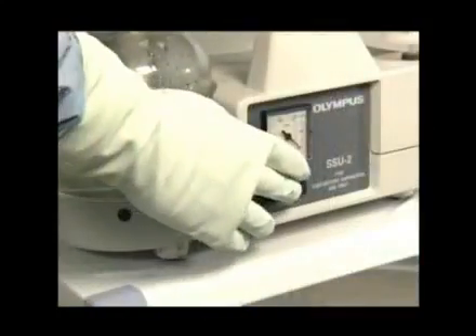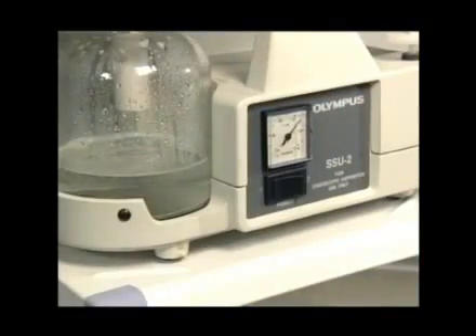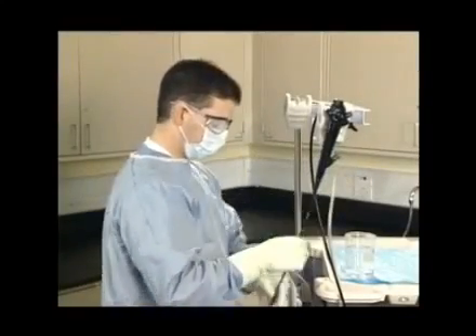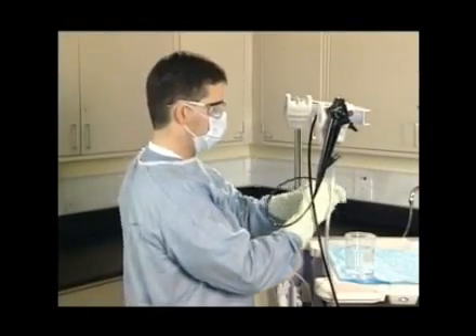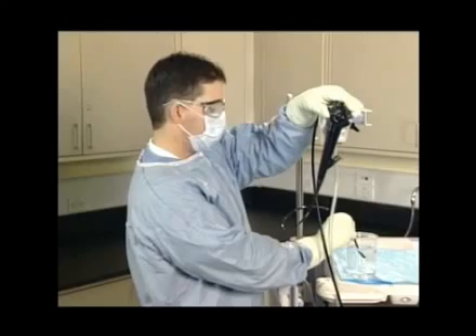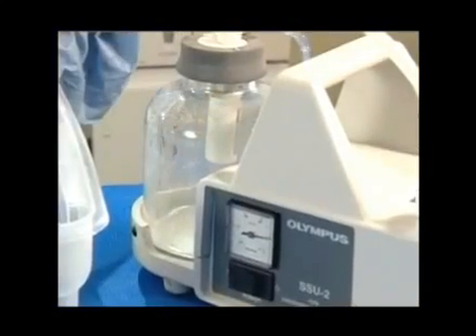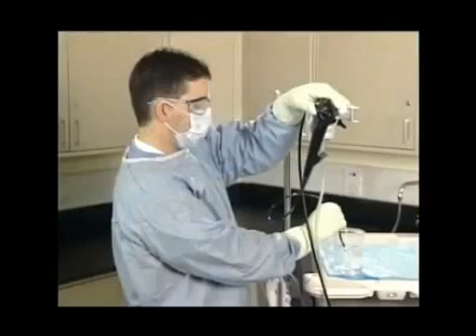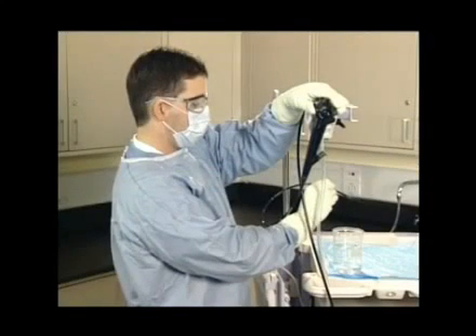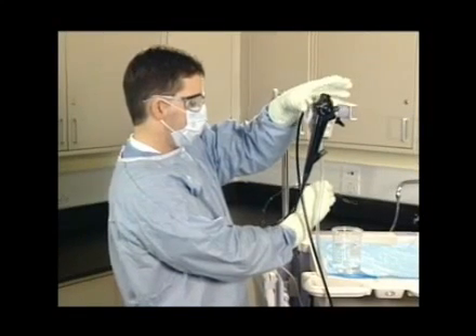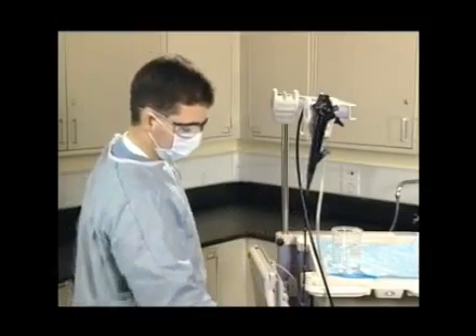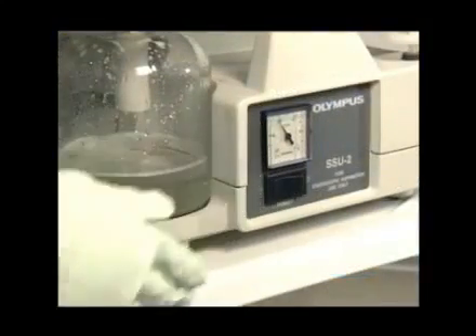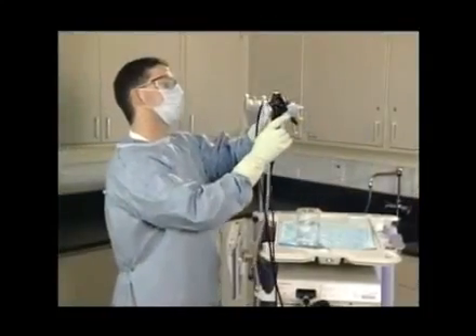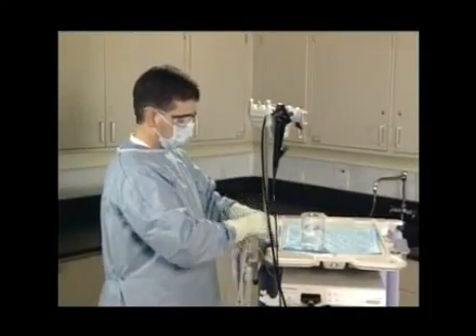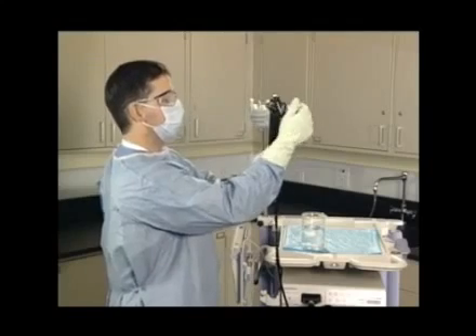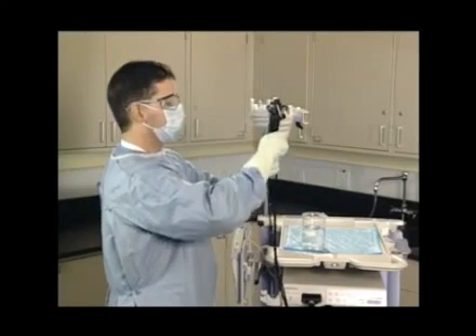Next, turn on the suction pump or connect the bronchoscope to wall suction. Make sure that the biopsy valve is still attached. Immerse the distal end of the bronchoscope in detergent solution and aspirate for 30 seconds. Remove the distal tip from the detergent and aspirate air for 10 seconds. Now turn off the suction pump. Disconnect the suction tube and remove both the suction valve and the biopsy valve. Both of these items are intended for single use and should be discarded.